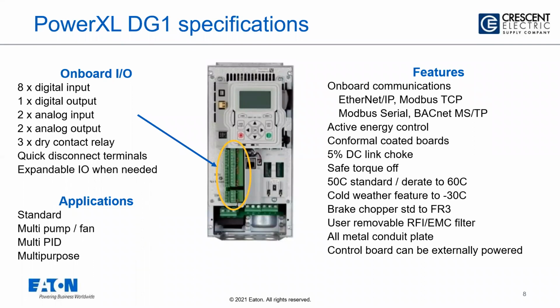And another great feature with this, and this is wonderful in the water wastewater space, is that if you use an input isolation contactor, you can actually power the control board from an external power supply, which keeps the communications active. So then you can trigger that external contactor from an input standpoint over communications to power up the power section of the drive. So, way too many features to have in one slide, but I just wanted to give you a little understanding of some of the features of this particular product.